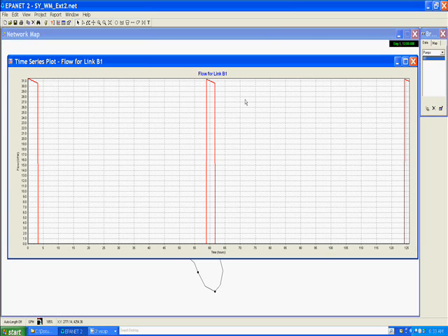You can note that the slope signifies when the pump comes on, the tank is at a lower level, and as it pumps and the tank fills, the pump has to put more energy in against the head that the tank is supplying, and therefore the pumping rate goes down. And that's what we'd expect, and this is a good sign with our model.